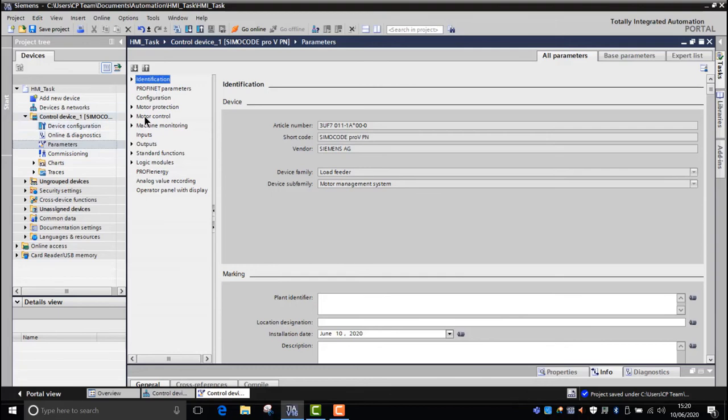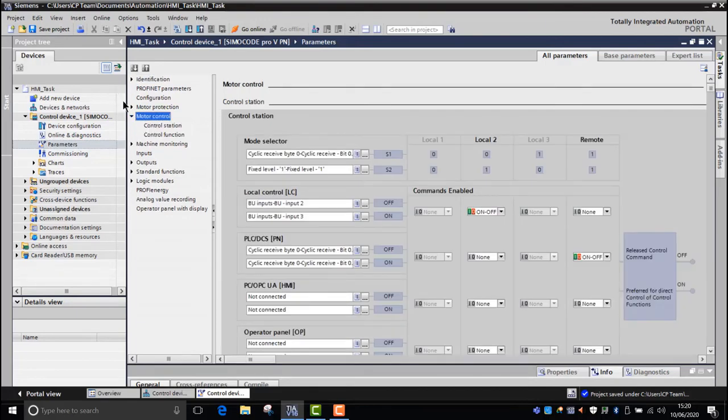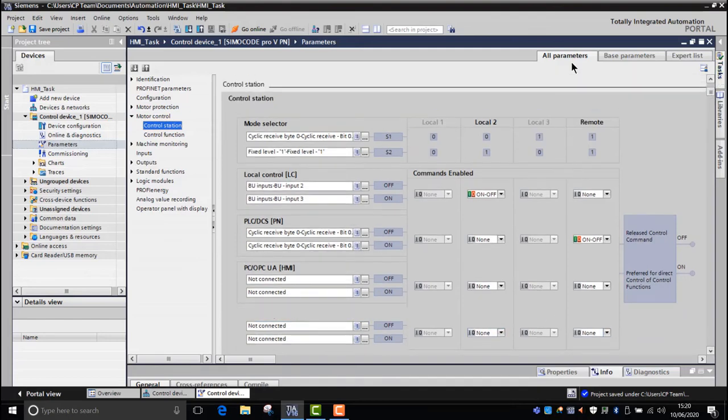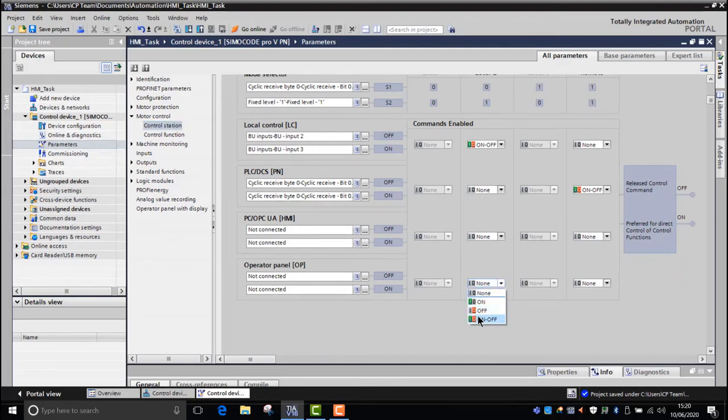Well, the only thing that we need to edit is the motor control station. So in motor control, in control station, you can see here the operator selection has been turned off and minimized. We're only going to be entering local two. So with that in mind, we need to switch local two on here and we want an on and an off command. So we'll select that.